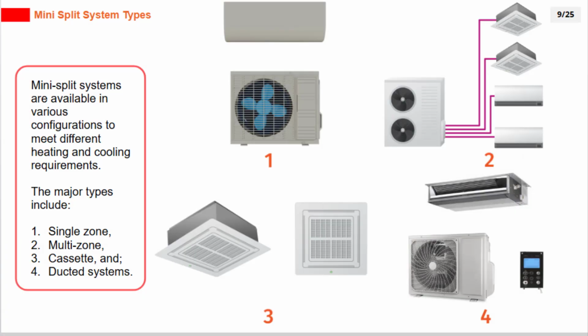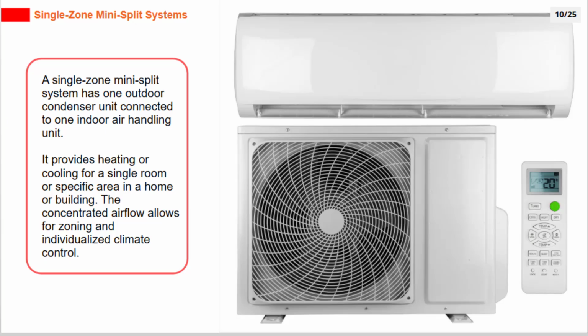Mini-split systems are available in various configurations to meet different heating and cooling requirements. The major types include single-zone, multi-zone, cassette, and ducted systems. A single-zone mini-split system has one outdoor condenser unit connected to one indoor air handling unit. It provides heating or cooling for a single room or specific area in a home or building. The concentrated airflow allows for zoning and individualized climate control.